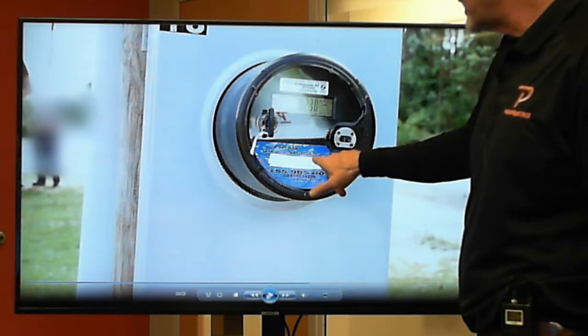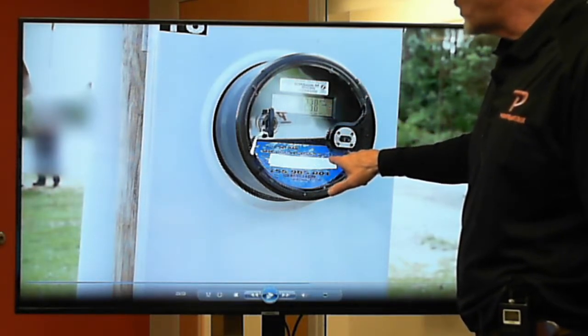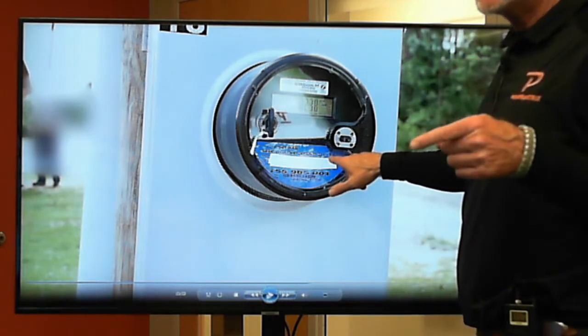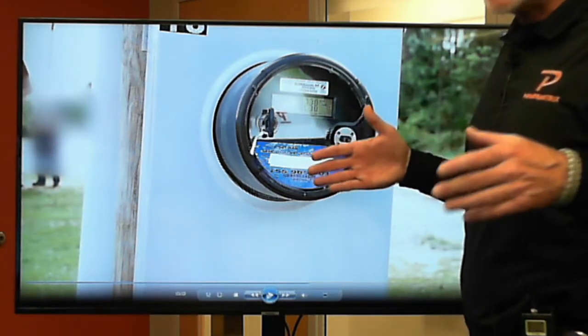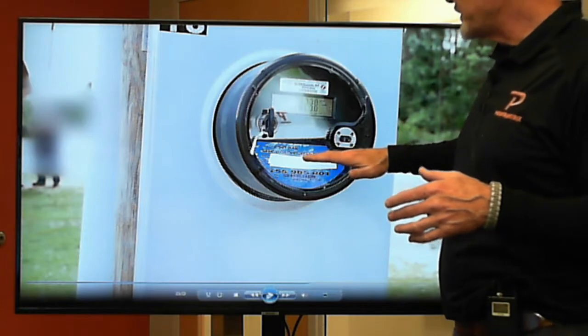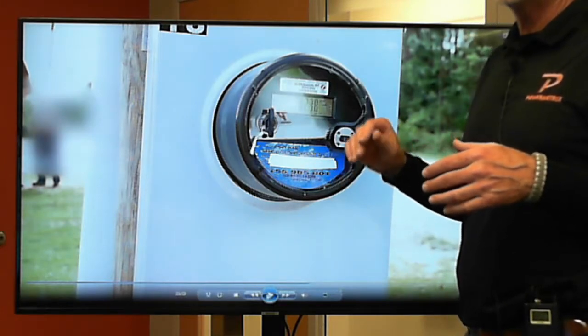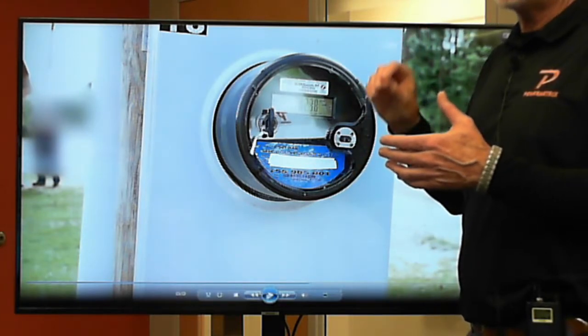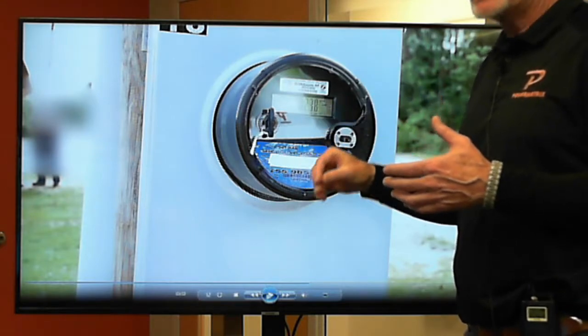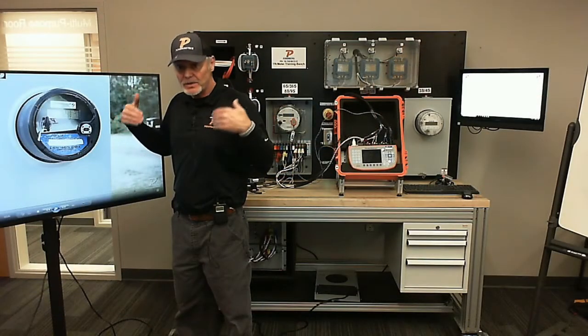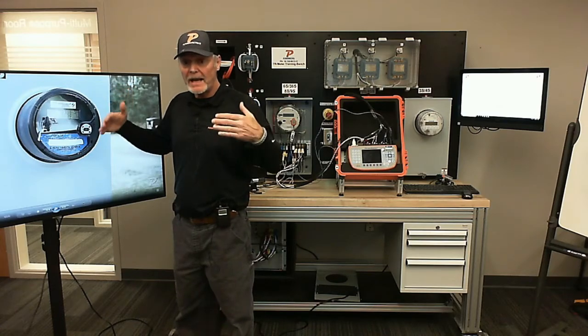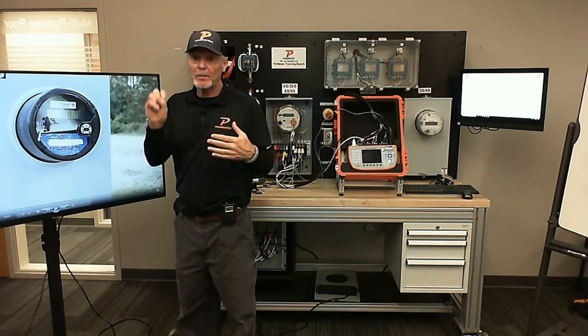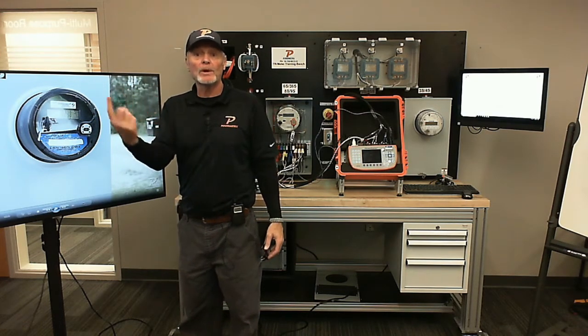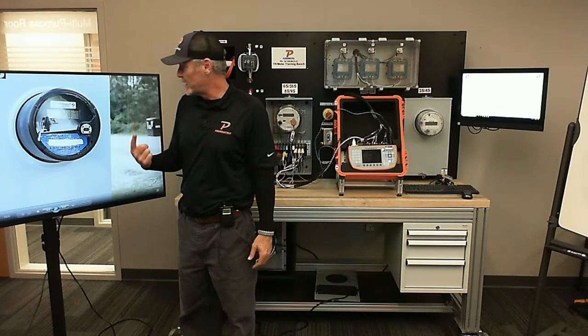Then down here, you've got the K sub H is 1.8. What that means is, we call it K sub T for testing, but we're saying, okay, for every 1.8 watts, I should get a pulse. So that's what you keep in mind as you're doing your testing, okay? Every 1.8 watts on that meter, I should get a pulse. Back in the day, it was 1 revolution of the old electromechanicals, right?